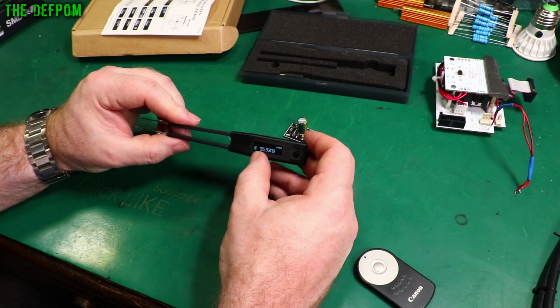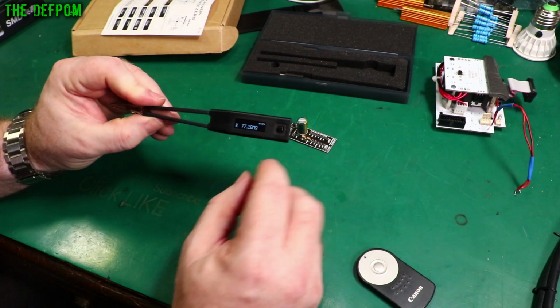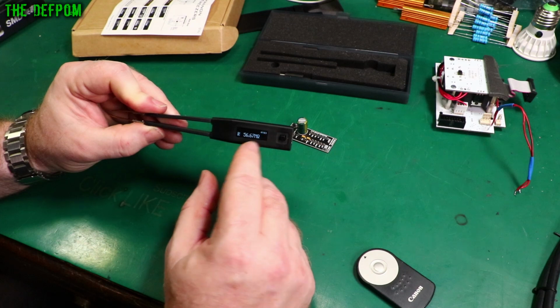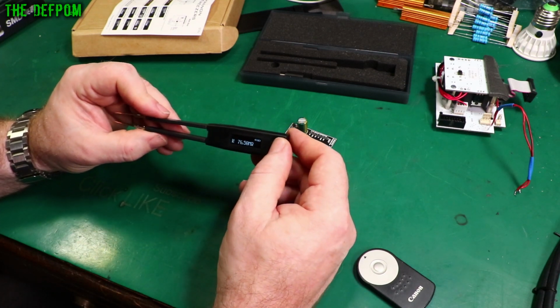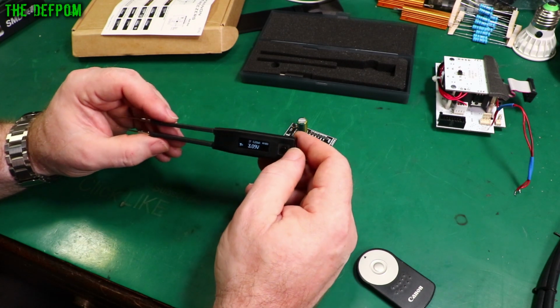So I tried this thing on the calibrator. I put it on the DC resistance mode. I started off as an open, then I went straight to a short on the resistance mode, and this kind of locked up. I did actually eventually get a reading like 100 ohms, and then that sort of stuck on the display, and even when I went out of that mode and into other modes, it didn't actually recover. That was quite interesting. It's got like a bit of a bug there somehow.